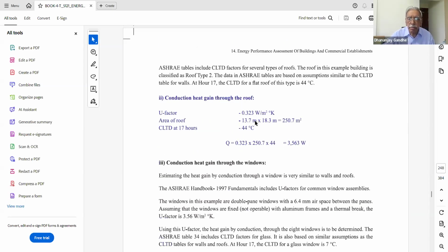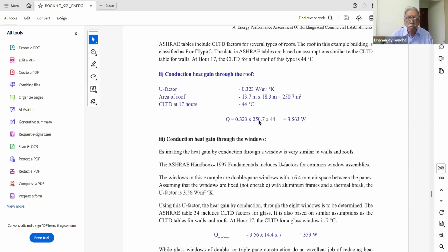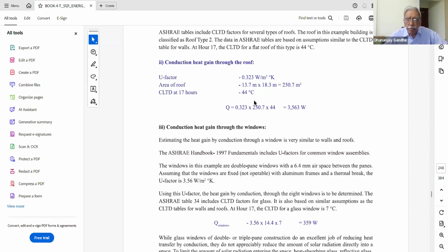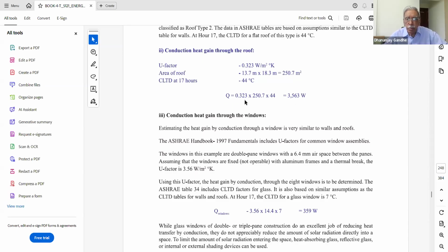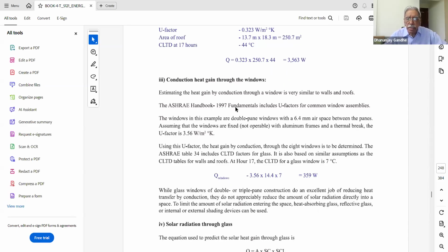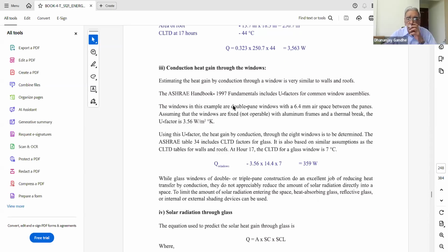Okay. Similarly, heat gain through the roof can be calculated using similar factors, by using the roof area, which is mentioned here. The U factor for the roof will also vary, and the CLTD for the roof will of course be different, because the roof outside temperature is going to be high, so the temperature difference is going to be high. So it is 44. This multiplied by 0.32 multiplied by 13 multiplied by 44 gives the heat gain through the roof. Similarly, one can calculate the heat conduction through the windows.